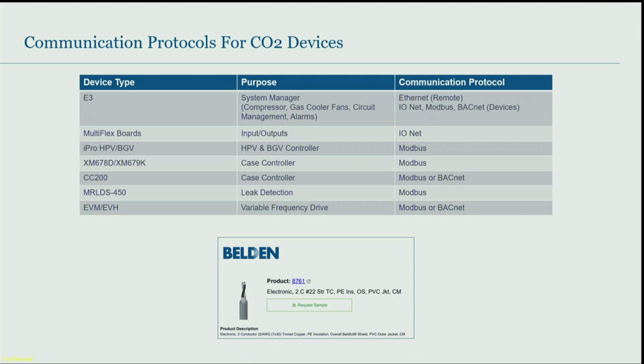So when you're laying out your network, that's probably one of the most important pieces to get everything communicating. Which COM ports, making sure things are set up on the right baud rates, setting up your addresses, and laying out those COM networks is really important. This is all the devices you'll need for a CO2 transcritical rack.